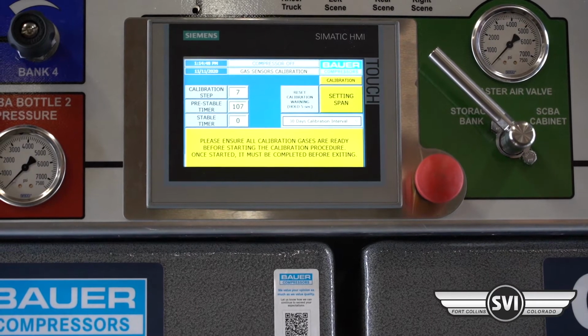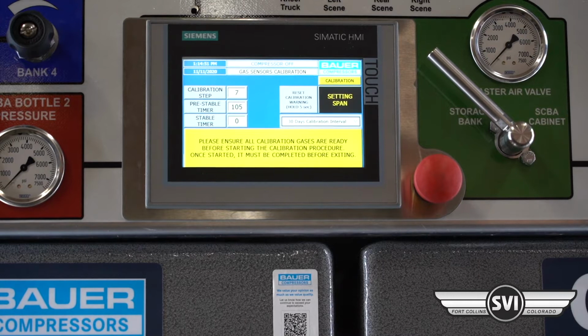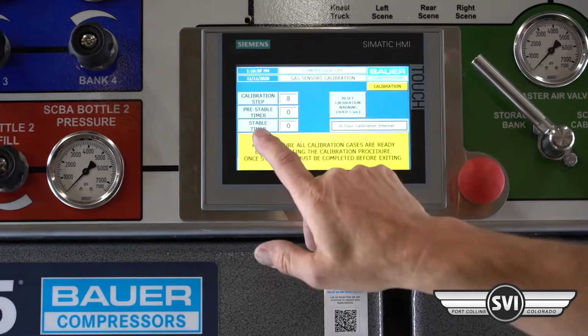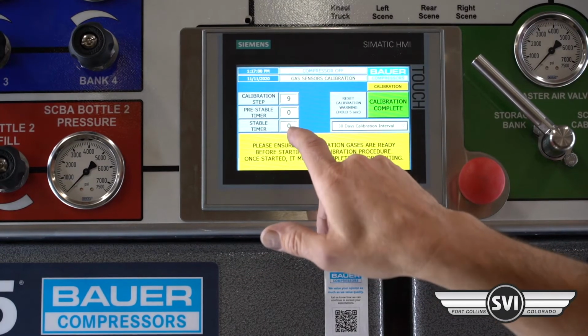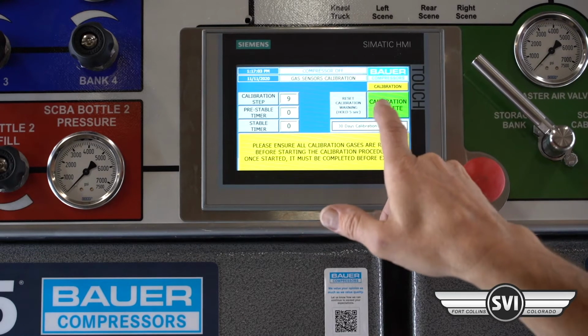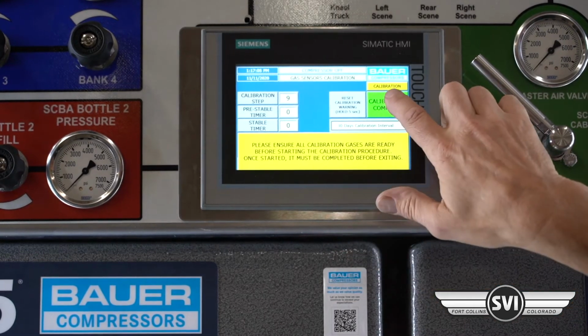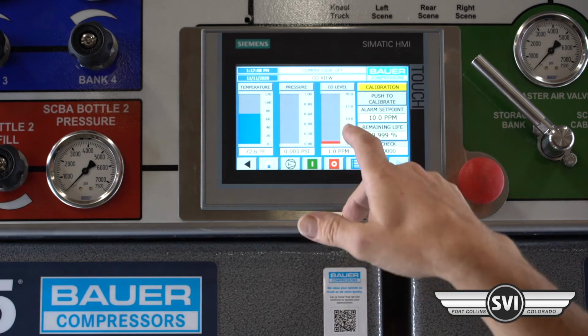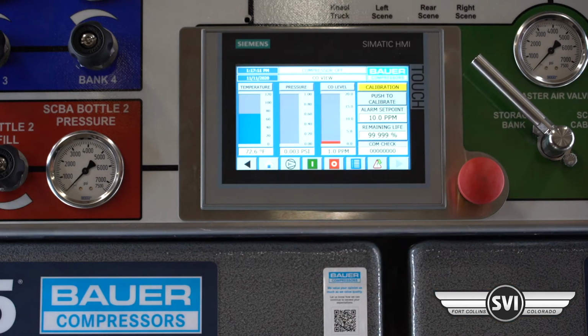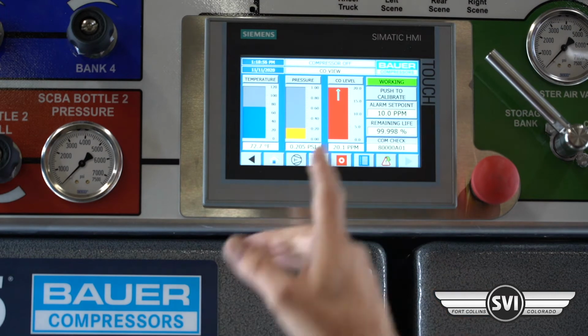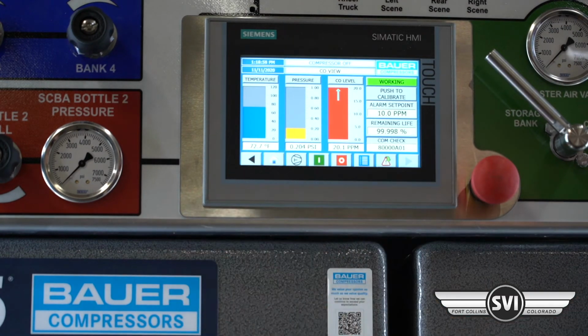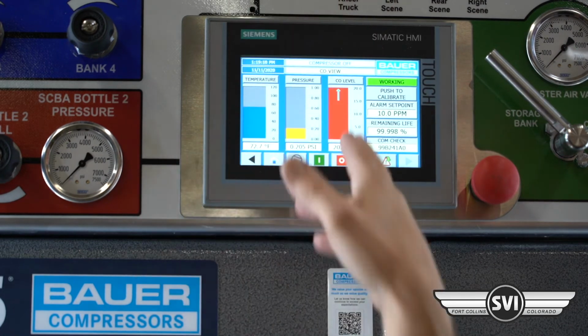So now we just wait for the longest 2 minutes of the day. The stable timer will start just a 20-second countdown. Once the stable timer is 0, it's going to go to green here. It's going to say calibration complete. I always push the green button, and then your PPM should jump up here in a second. Now I've got the 20 on there. I'm going to take that off. If I want to wait 5 or 10 minutes, that'll slowly dissipate, or I'll just screw the 0 on for about 5 seconds to purge that gas out of there.